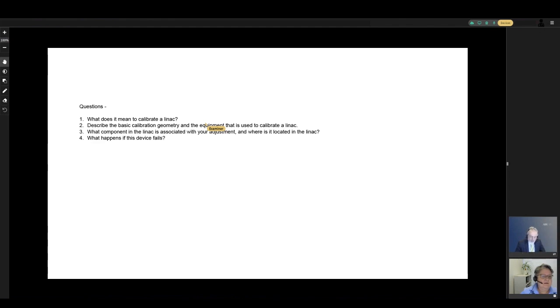Okay, so we're talking about the basic calibration geometry. What does the setup look like? Overall setup. I know you mentioned the equipment and how to make a particular measurement, but how's the machine set up, the Linac that is, relative to the water phantom? So the gantry, you set this up to 0. The tank is directly underneath the gantry. And then you set your jaws to a 10 by 10 so that you have a 10 by 10 field at the surface of the water. Okay, so where's the surface of the water relative? At 100 SSD.